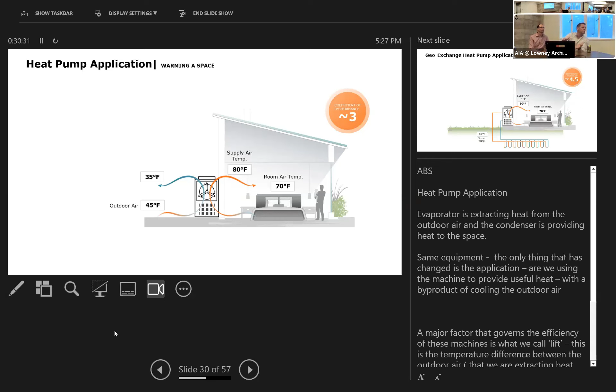And that brings me on to the next example, which is geo-exchange. We've got our heat pump outside again, but instead of extracting heat from ambient air, it's now got a hydronic loop and coils in the ground. So it's trying to extract heat from the earth. And in this case, it's wintertime, but the ground temperature is still about 60 F. And what you've achieved here is the temperature differential, the lift, is now going from 60 F to 80 F. So it's reduced from 35 degrees in the previous example down to 20 degrees.